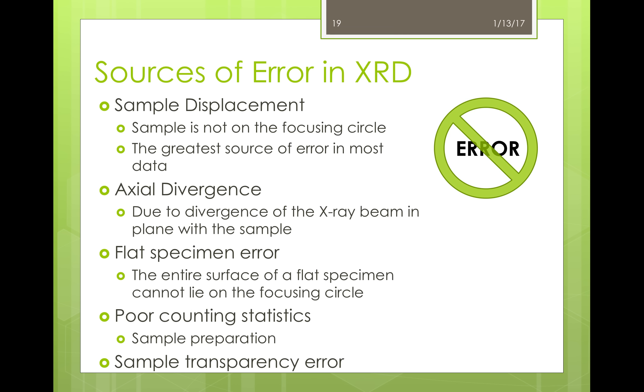There are a few very common sources of error when collecting data from XRD, and many of them can be easily avoided. The most common of all is sample displacement, meaning that the sample is not in the correct place and is not in the focus of the X-ray tube or the detector — so just put your sample where it's supposed to be. Axial divergence can be minimized with the primary and secondary optics, but if the X-ray is misaligned with the sample, it can cause divergence. A flat specimen error and poor counting statistics can both be avoided with better sample preparation. A powder sample should be thick enough to prevent the X-ray from passing all the way through it. Lastly, sample transparency can cause a shift in the peaks due to the diffraction beam being partially displaced, which can lead to inaccurate peak profiles.